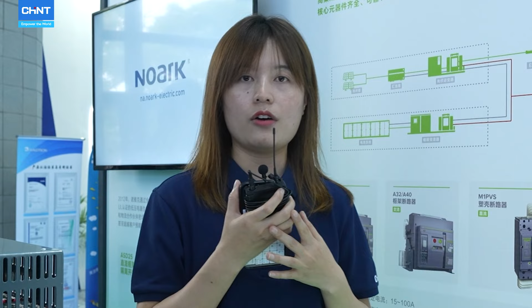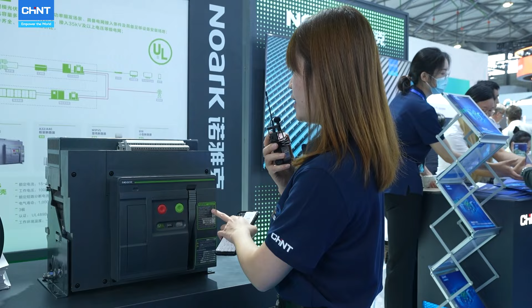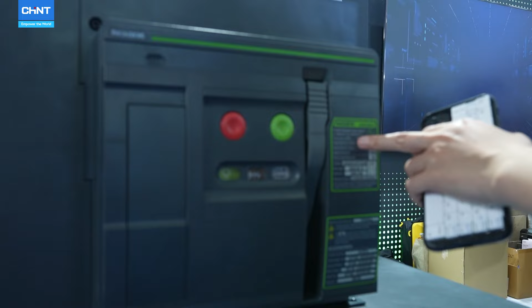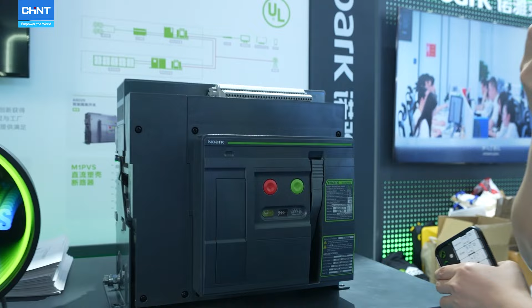Realizing the importance of this, NOARK has developed and released a variety of products complying with UL 489B and UL 489 Supplement SC. For example, this is our ASD25 DC circuit switch disconnector. It was certified according to UL 489B and UL 489 Supplement SC. It's used in central inverters to isolate the inverter from the solar field, and in energy storage systems it can be used to protect battery racks.